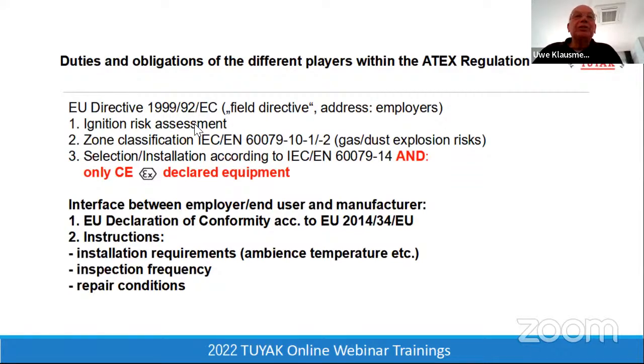The other directive, 1999/92, is the risk assessment directive. You have to take this on board before planning a facility with explosive hazards inside. Here you have to apply for the zone classification, part 79-10 and -1 for gas, and part 2 for dust explosion risks.